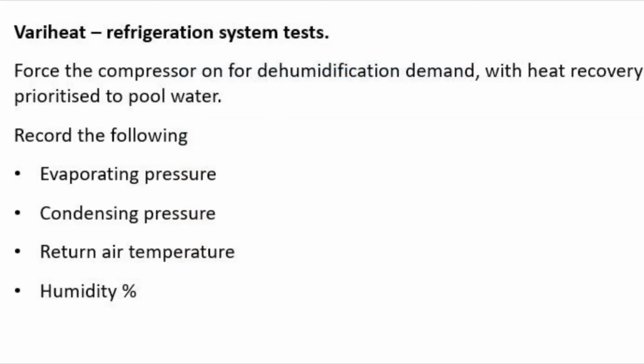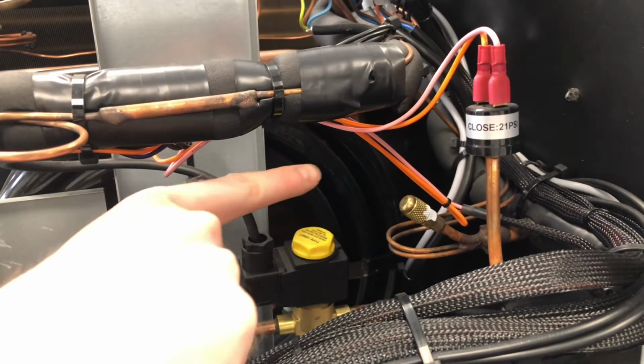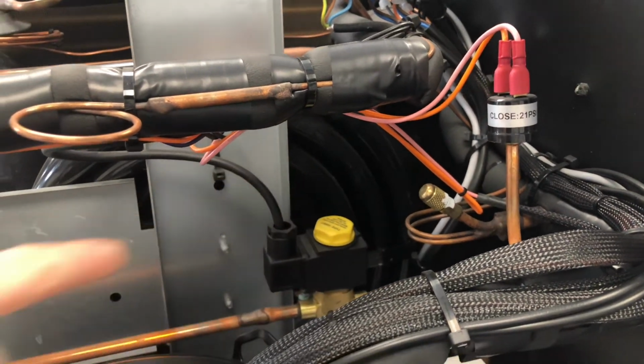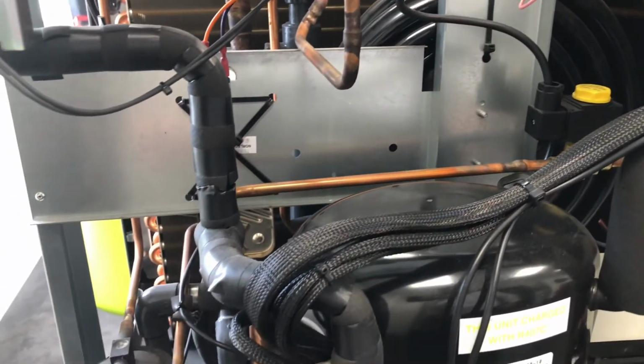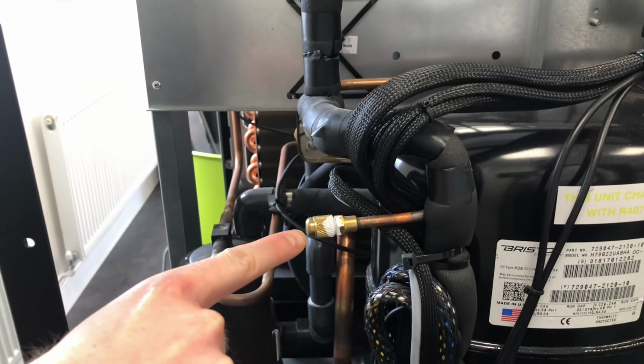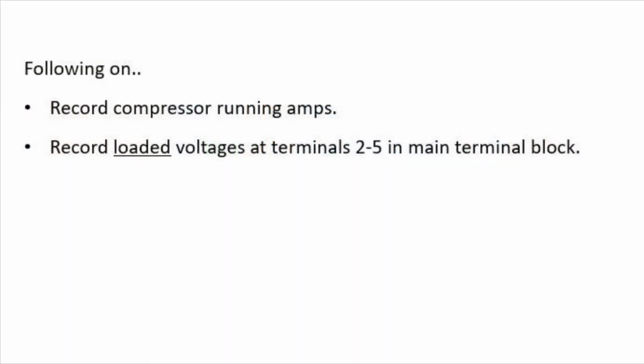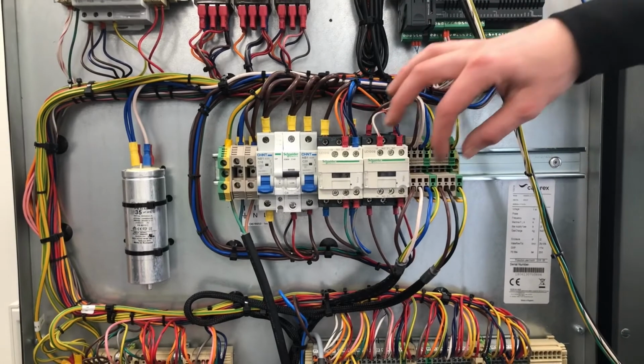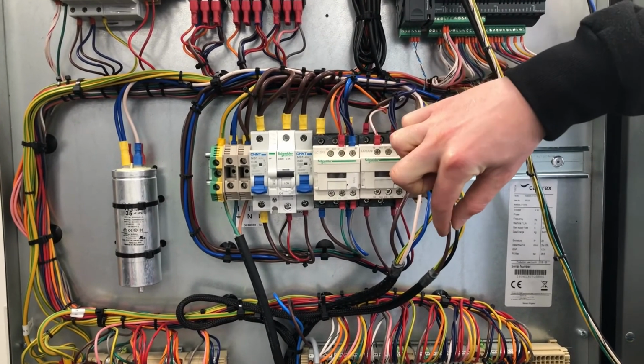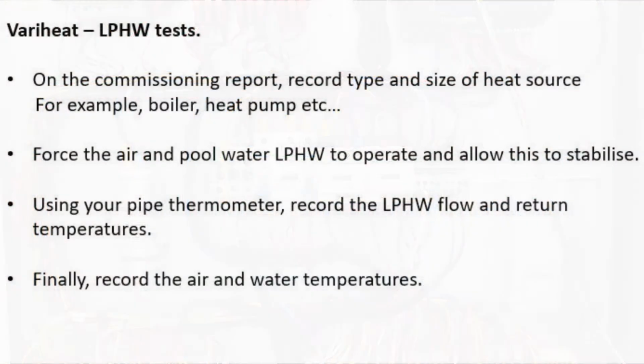Force the compressor on for dehumidification demand, recording the evaporating and condensing pressures by attaching refrigeration gauges to the service ports. Also, take note of the return air temperature and humidity. Follow on by recording the compressor running amps and loaded voltages in the main terminal block. To commission the low pressure hot water heating coil, follow the instructions as bullet pointed.